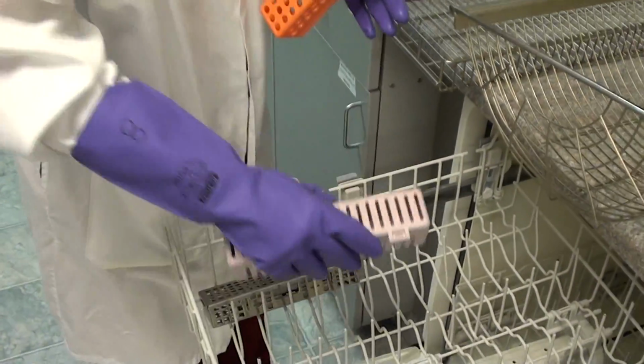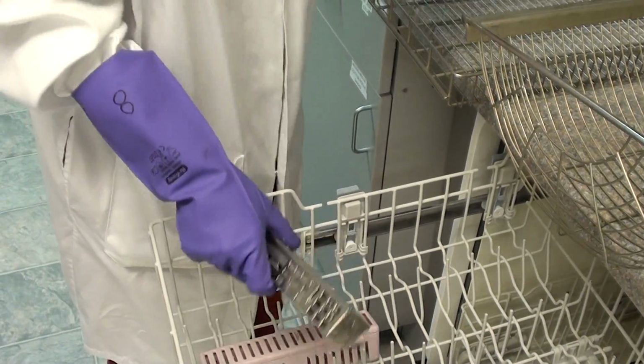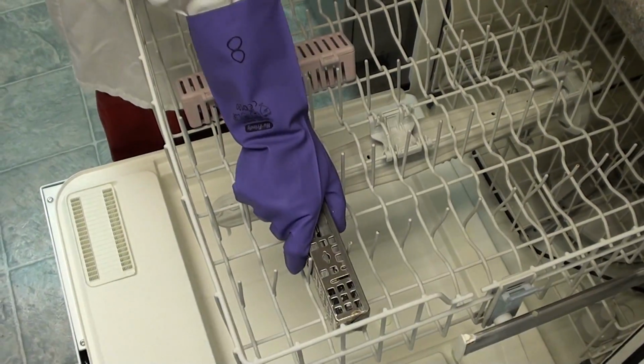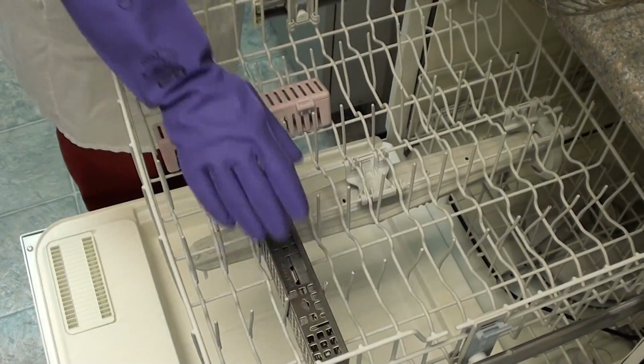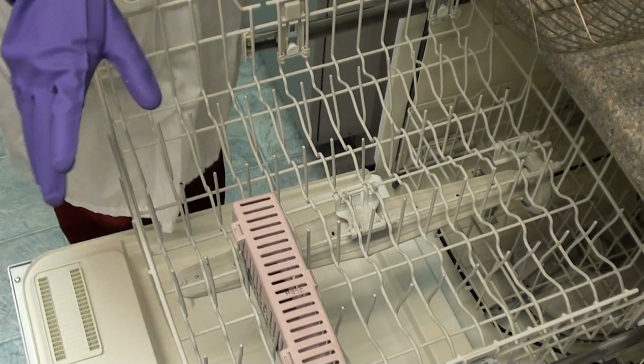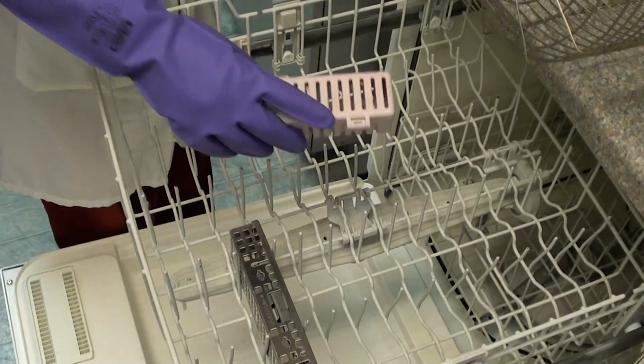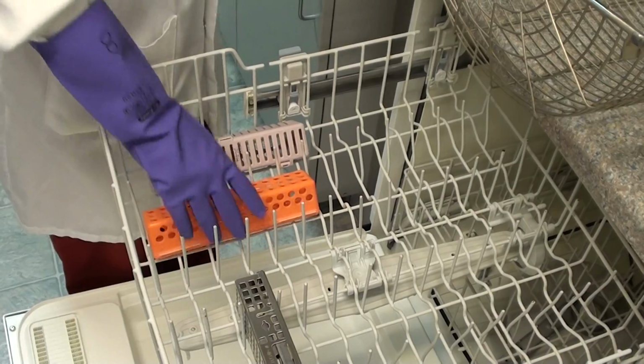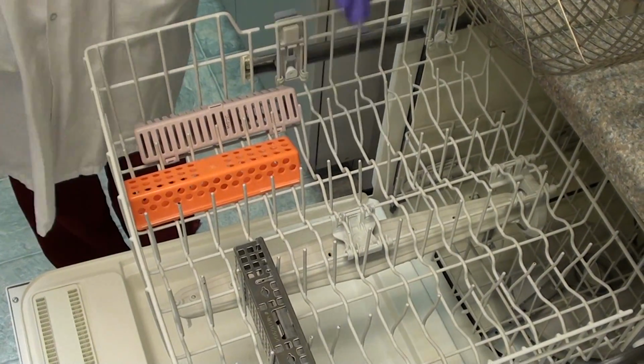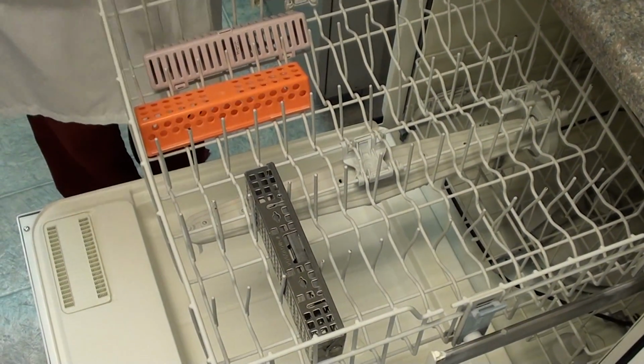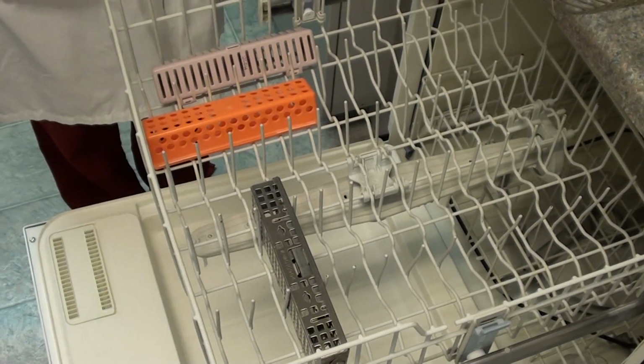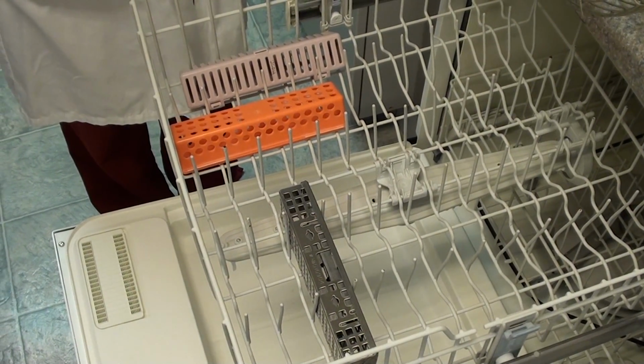Sometimes, it depends on the size, you can set them like this. On the top, you cannot double stack. This is a no-no on top, but on the bottom, you can. She's going to place the loaded instrument cassettes into the washer with sufficient space to allow water to access the sides, top, and bottom of each cassette. And as she mentioned, do not overload.